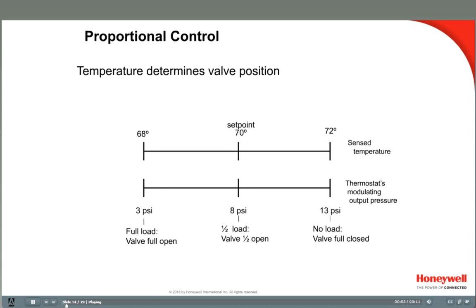The operation and calibration of pneumatic controllers makes more sense when we thoroughly understand proportional control principles. Set point is the desired temperature, and control point is the current room temperature. The difference between these two temperatures is called offset. Throttling range is found in all modulating control systems, from pneumatic to modern DDC systems. Throttling range is the change in degrees that will cause the valve to go from full open to full closed. With a set point of 70 degrees and a throttling range of 4 degrees, the range is 68 to 72 degrees, and the valve or damper modulates to a partially open position when the control point is within this range.